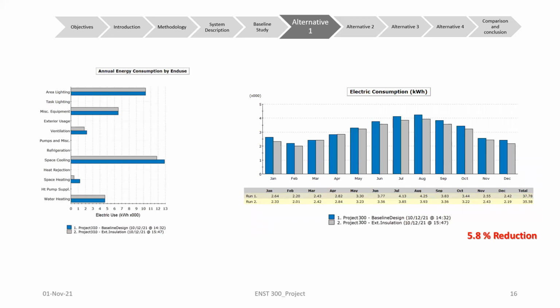The first figure compares the annual energy consumption of the base case to that of alternative 1. It shows that adding insulation to all of the exterior walls has led to a noticeable decrease in the electric consumption. The electric load related to lighting, electrical equipment, and water heating has not been affected by the external insulation. In fact, these are considered internal heat sources, while the external insulation attenuates external heat gains. The load related to cooling, heating, and ventilation showed a considerable decrease due to the addition of outside insulation. As a matter of fact, when external insulation is used, the heat transfer from the exterior to the interior of the house is reduced. Consequently, the load needed to bring the temperature of the inside air to required levels is reduced. In conclusion, this alternative showed an approximately 6% decrease in annual energy consumption compared to the base case.